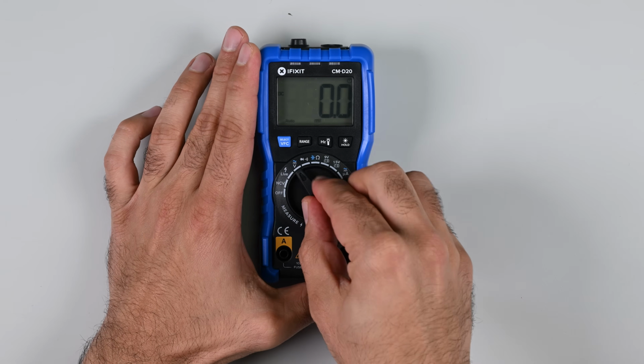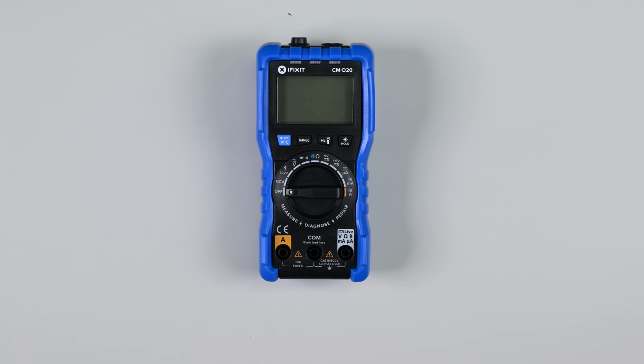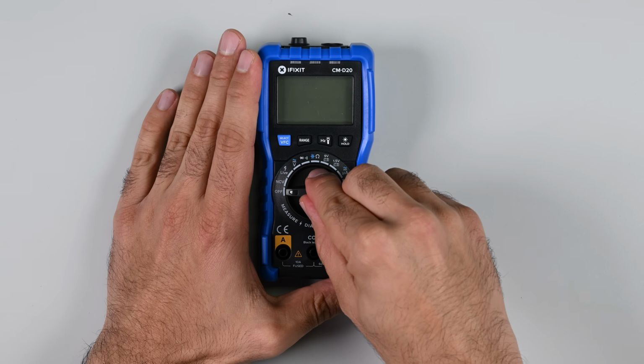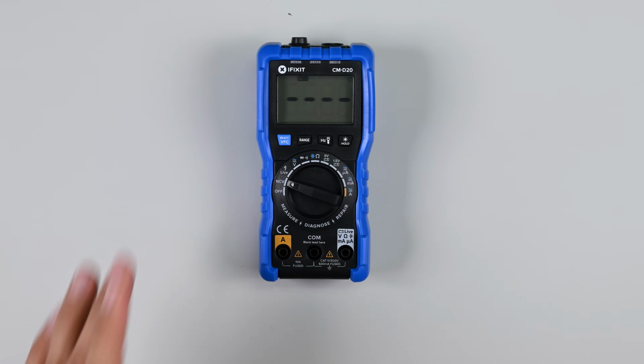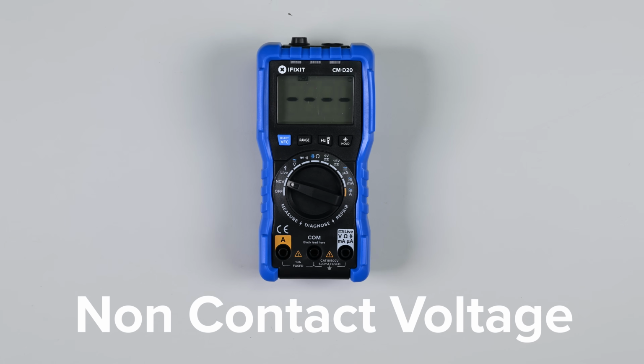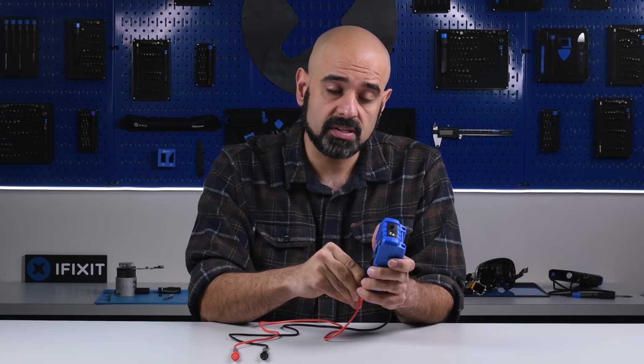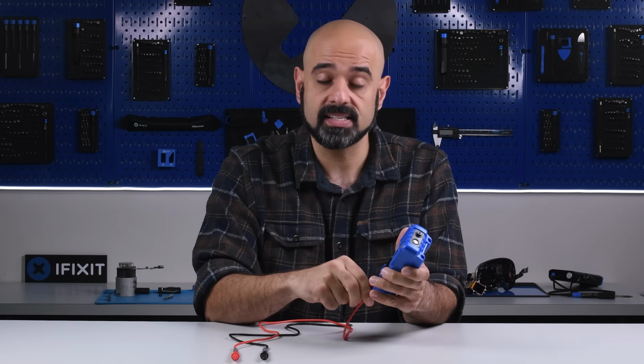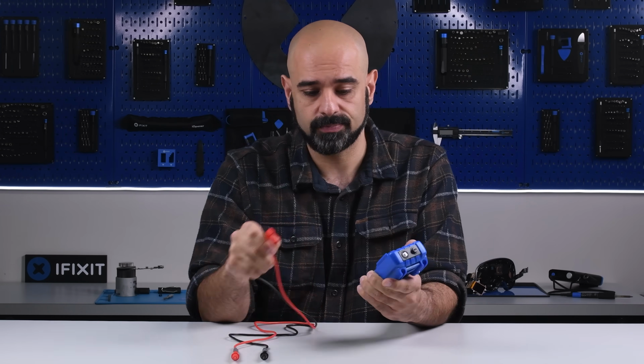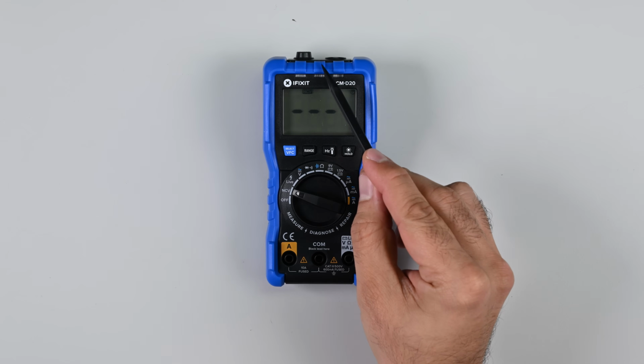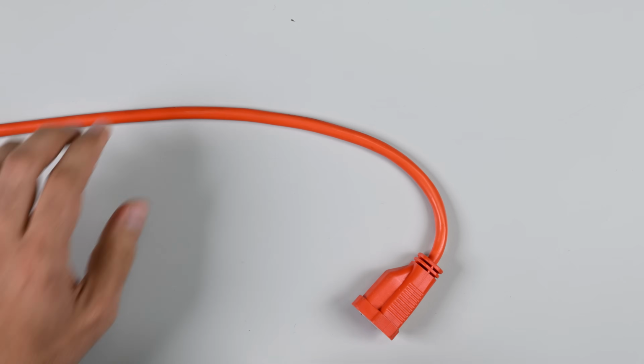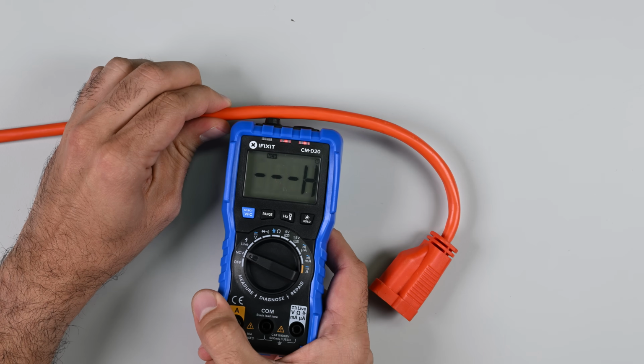Starting from the far left, the multimeter is set in the off position and powered down. The next setting powers the device on and sets it to NCV, which stands for non-contact voltage for sensing mains AC voltage. So we're not going to need our probes for this one, because as the name suggests, this is going to be a non-contact test. The NCV sensor is the nub at the top of the multimeter. Simply touch this to a wire. If it has AC running through it, it'll beep.